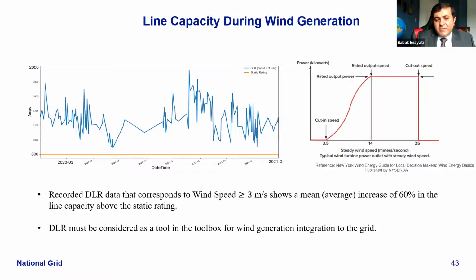Back to the point Jay was making about moving static ratings: in the planning process, if the line is close to wind turbines, it's always exposed to higher wind speed. This data shows there's a possibility to move the static rating slightly up to allow more capacity in the planning process.